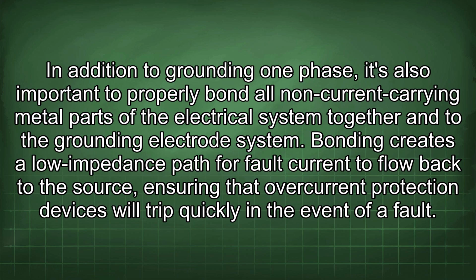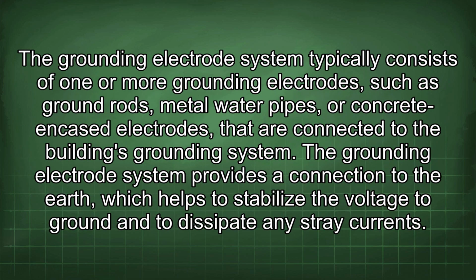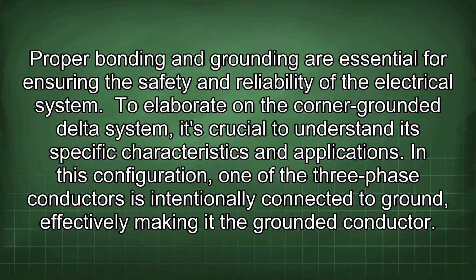In addition to grounding one phase, it's also important to properly bond all non-current carrying metal parts of the electrical system together and to the grounding electrode system. Bonding creates a low impedance path for fault current to flow back to the source, ensuring that overcurrent protection devices will trip quickly in the event of a fault. The grounding electrode system typically consists of one or more grounding electrodes, such as ground rods, metal water pipes, or concrete encased electrodes that are connected to the building's grounding system. The grounding electrode system provides a connection to the earth, which helps to stabilize the voltage to ground and to dissipate any stray currents. Proper bonding and grounding are essential for ensuring the safety and reliability of the electrical system.